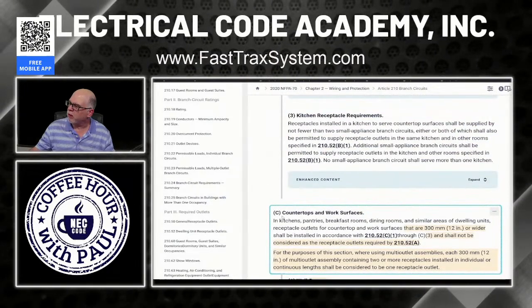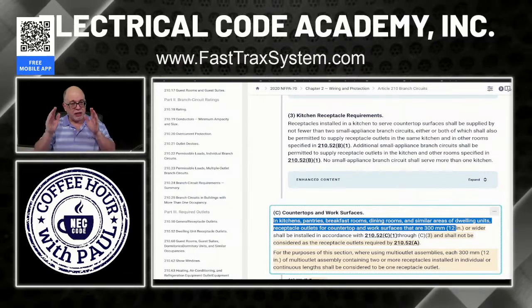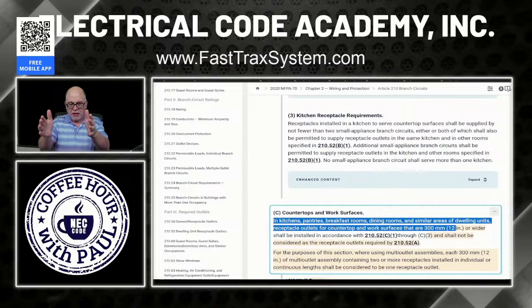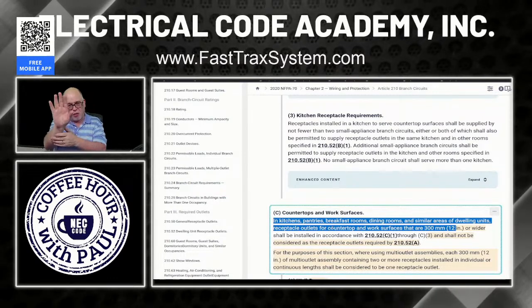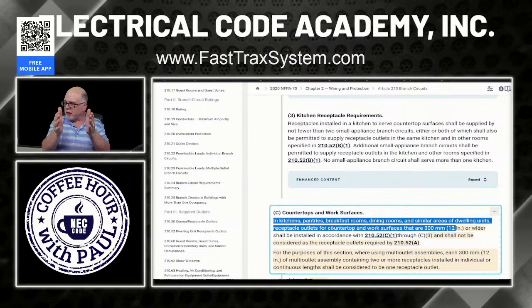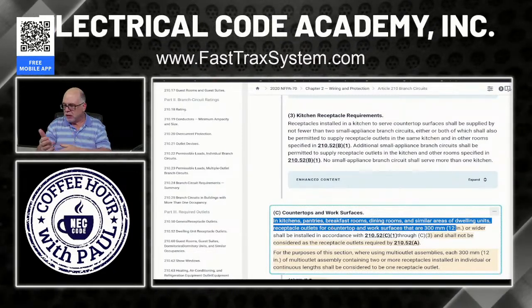Oh, by the way, since we're here, this one right here for the 12 inches means that on the countertop, if you have an efficiency apartment and a small countertop, if it's at least 12 inches wide, then a receptacle has to be there. If it's only 6 inches wide, then you don't have to have a receptacle there. That's what that means. So every countertop or workspace that's at least 12 inches has to have a receptacle.